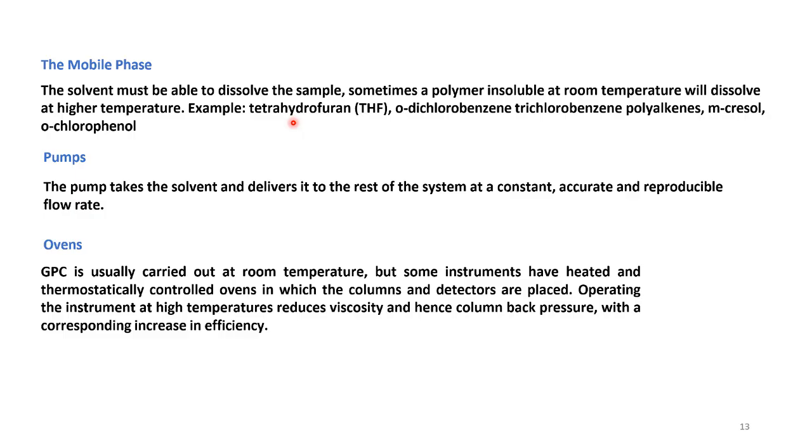Then the pump. The pump takes the solvent and delivers it to the rest of the system, the column, and then passes it through the different instruments. So it makes a constant flow all over, and it has to be an accurate and reproducible flow rate. That is why we need very efficient pumps.